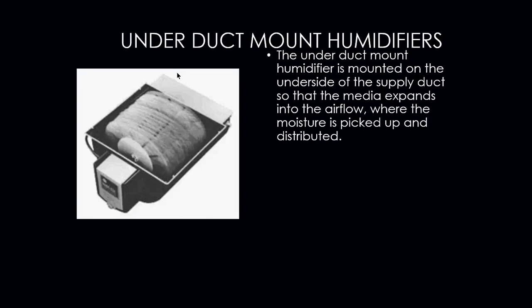Your under the duct type humidifiers, these are mounted on the underside of any supply duct so that the media expands into the airflow where the moisture is picked up and then distributed. So these types of humidifiers are going to be put only on the supply duct. They cannot be installed on a vertical piece of ductwork. They have to be installed on a horizontal piece of ductwork.